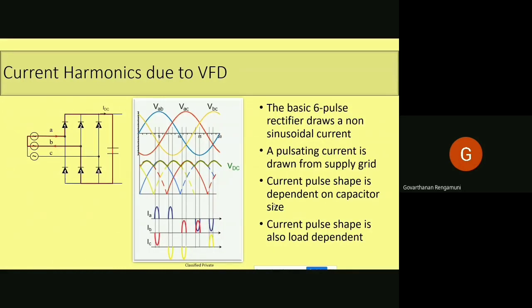Now we can see what the current harmonics injection is because of the variable frequency drive. As I already said, we need to consider the front end, meaning the three-phase rectifier, and how it is injecting the harmonics into the grid. According to the principle of the three-phase rectifier, input current is not sinusoidal in nature. Even though there is a resistive load at the output of the three-phase rectifier, you will not see a sinusoidal current at the input side. Already it is distorted. As I already mentioned, if the shape of the waveform is not sinusoidal, then you are generating more harmonics. So considering that, you have already started polluting the grid.